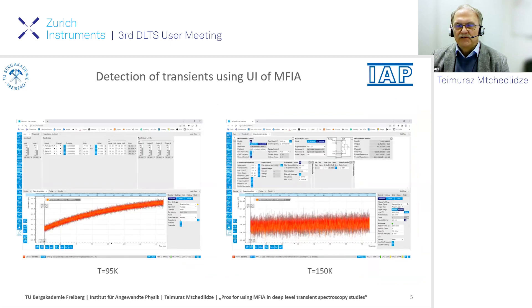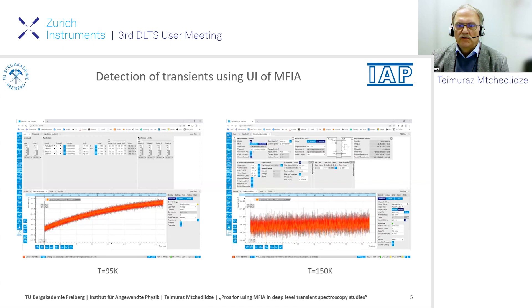As it was nicely presented by Ron today, one can observe capacitance transients. You see that at 95K there is a transient of capacitance, and at 150K there is no transient. Before the actual DLTS spectrum measurements, we just recommend choosing all MFIA settings like gating, timing, frequency, and so on from the user interface. Then these parameters can be inputted in the measurement program, which is necessary for temperature management, recording a data file, and automation of the whole measurement routine.